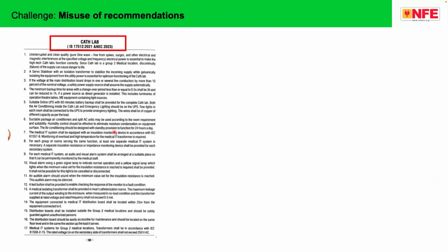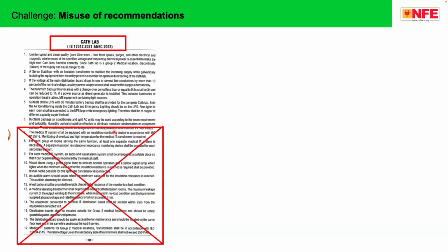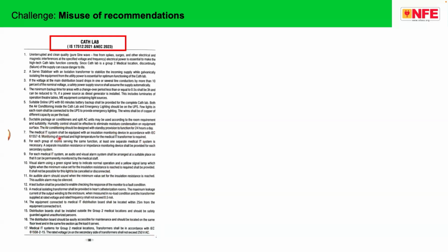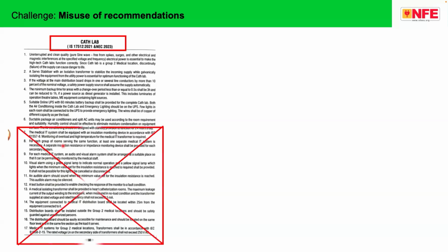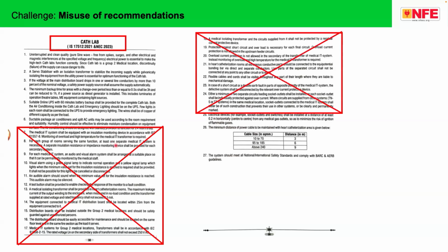Now there is a misuse of recommendation. Recently, I saw this: a cath lab supplier. They are asking from here, you can see serial number 7 onwards, to put a medical IT system for a cath lab. Absolutely, this is wrong. Medical IT systems are possible maximum up to 10 kilovolt-ampere. The maximum leakage current has to be limited to 0.5 milliampere. So this is a misuse of the recommendation by the manufacturer.